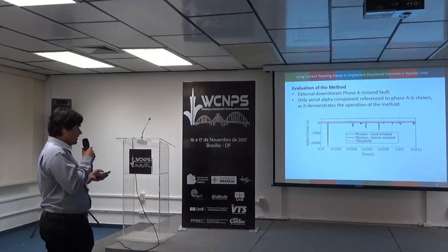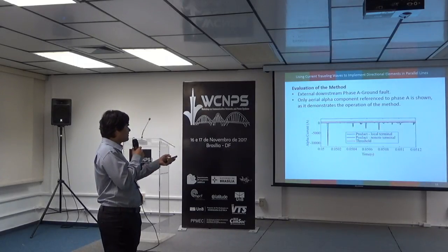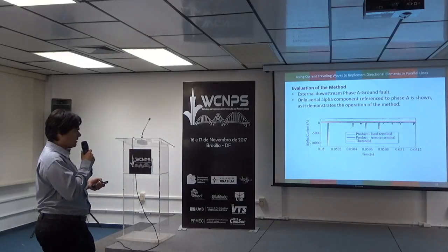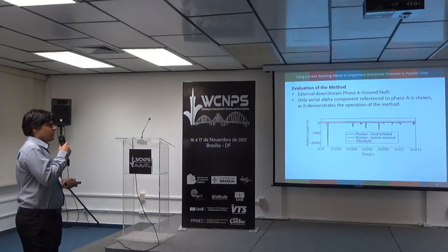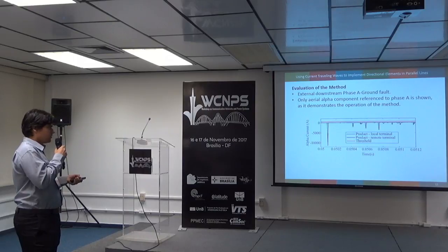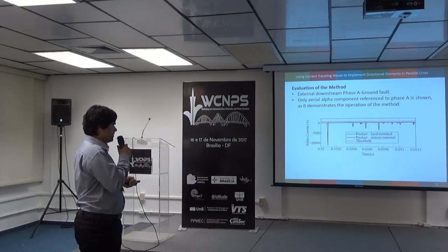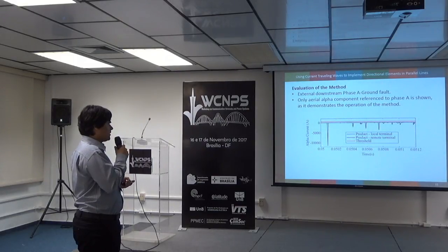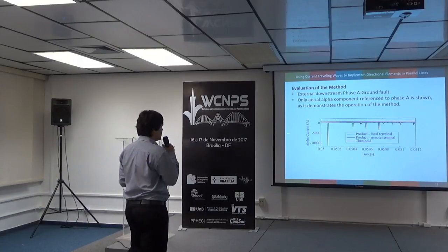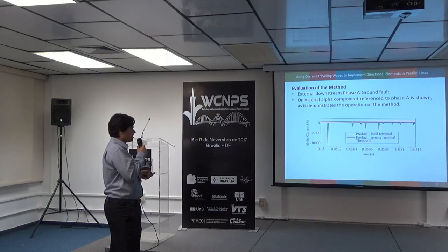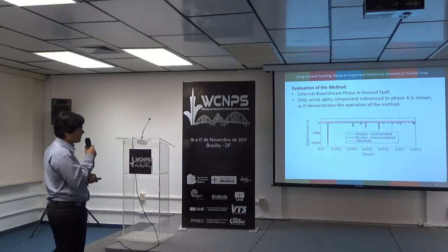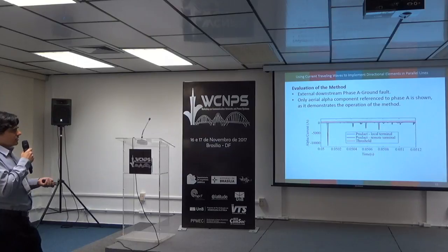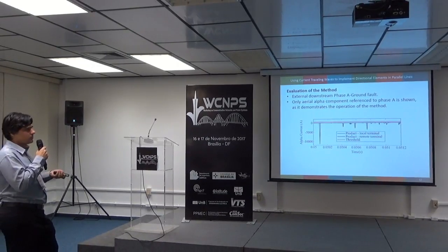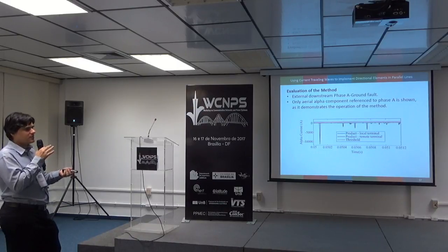External downstream faults. In this case, we see that no fault was detected in the local terminal. That is the farthest from the fault. The fault is closest to the remote terminal. As you can see, the product calculated is negative, and the blue line that you cannot see here is near 0 because of wave interference, but it does not indicate an internal fault. And important, we show that the method does not indicate a wrong forward fault.